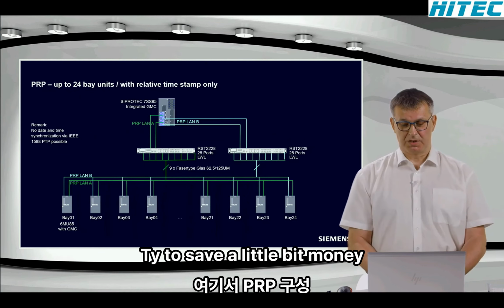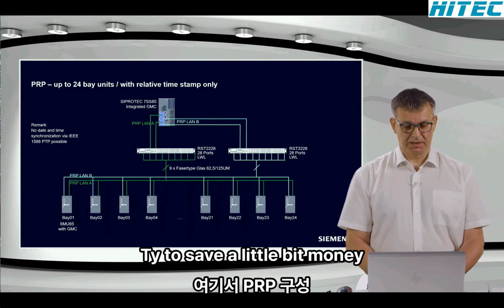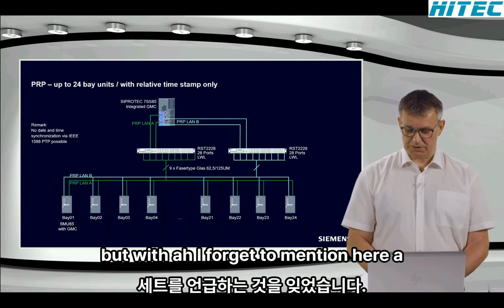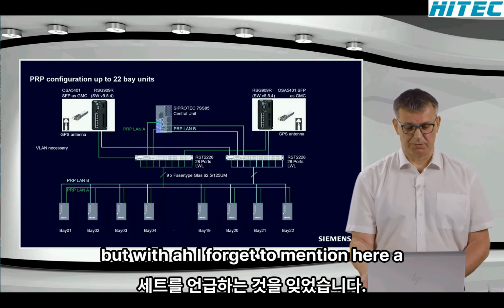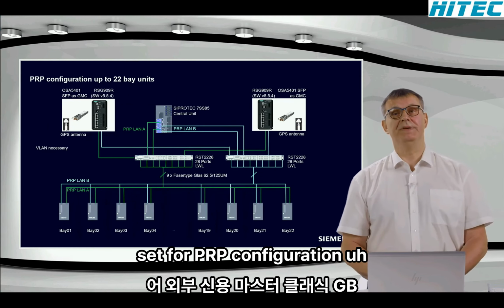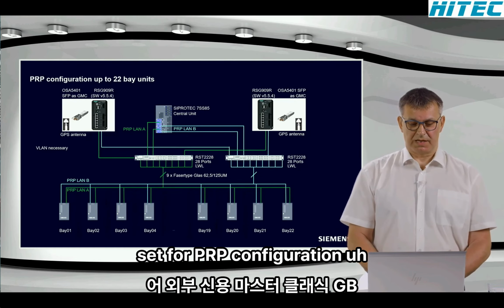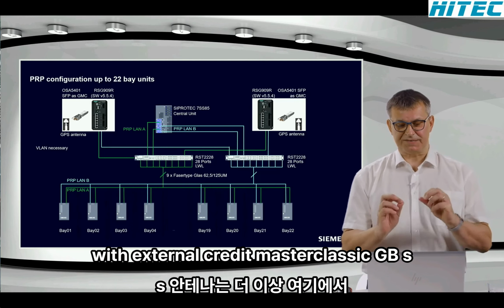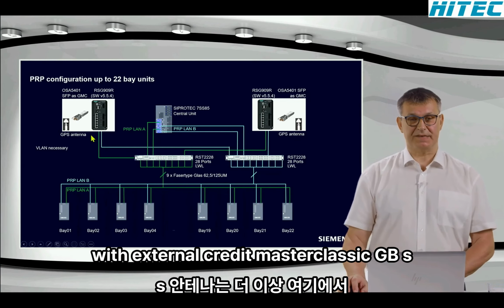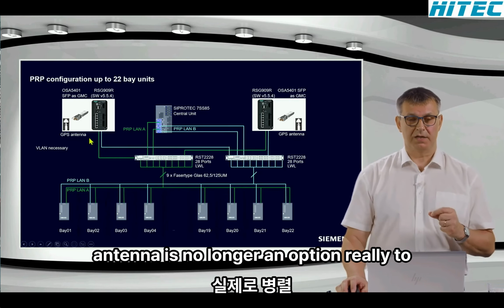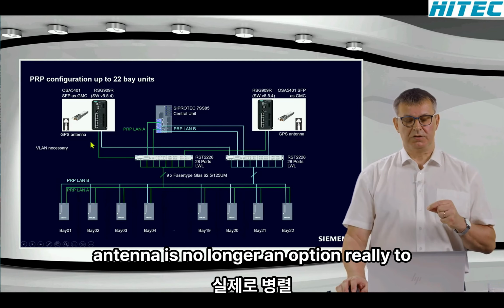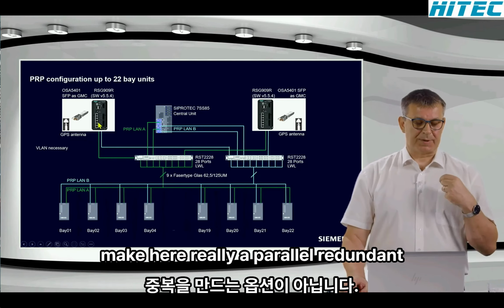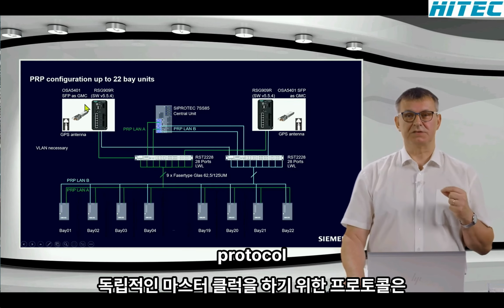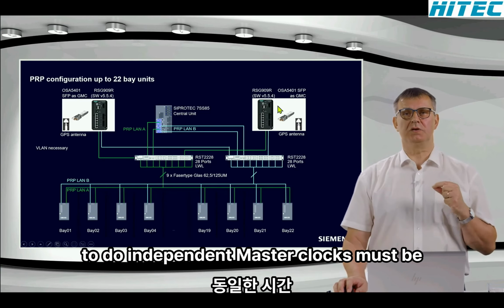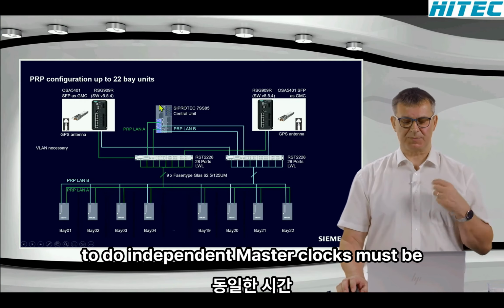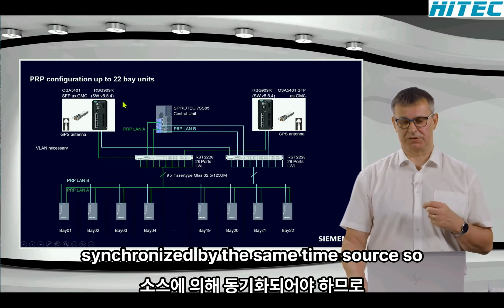Another possibility to save a little bit of money, but I forgot to mention that for PRP configuration with external grandmaster clocks, the GPS antenna is no longer an option. Really, to make a parallel redundant protocol, the 2 independent grandmaster clocks must be synchronized by the same time source.